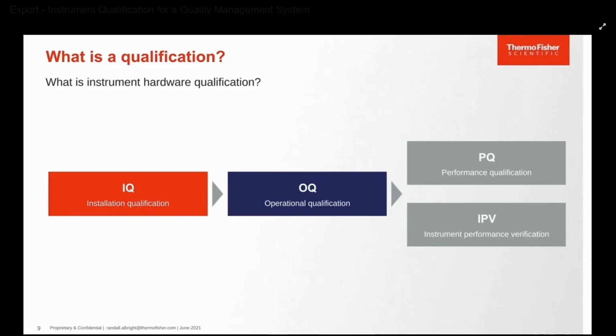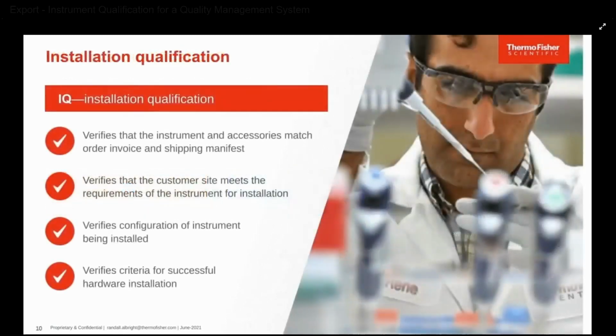Here is where Thermo Fisher Scientific Life Sciences Group differentiates RUO and the IVD DX instrument products. The PQ is performed with the DX or IVD instruments, and the IPV or instrument performance verification is performed with the RUO instruments. To be clear, for our audience, this is strictly Thermo Fisher Scientific's nomenclature to differentiate our instrumentation. For our purposes, they are equivalent. All three components make a completed qualification protocol. We will be speaking in more detail of each of the qualification components as well as the difference between hardware PQ and workflow PQ. Moving on to the details.